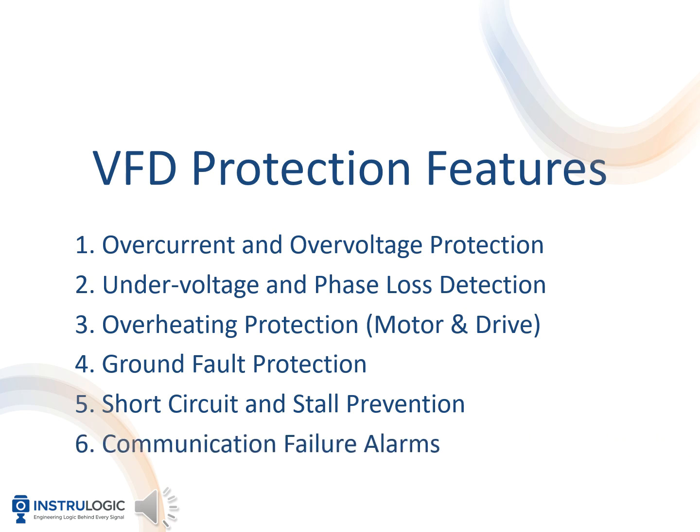Now let's talk about the protection features of a VFD, which make it safer and more reliable than traditional starters. A VFD includes several built-in protections: overcurrent and overvoltage protection to prevent damage when current or voltage exceeds safe limits; undervoltage and phase loss detection to ensure the motor does not run under poor supply conditions; overheating protection for both the motor and the drive; ground fault protection to detect leakage current and prevent electrical hazards; short circuit and stall prevention; and communication failure alarms when there is a loss of signal from a PLC or sensors. These features help maintain system safety, reduce downtime, and protect expensive equipment.